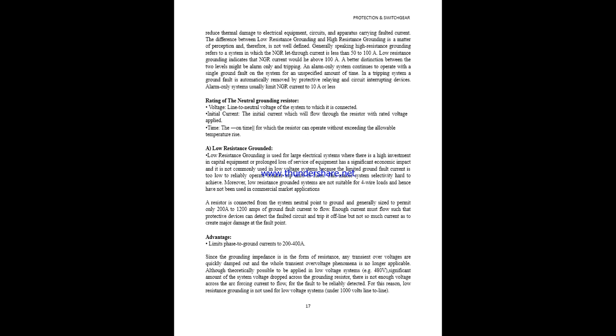There are two different types of resistance grounding, which are low resistance grounding and high resistance grounding. The ground fault current flows through either type of resistor, and when a single phase faults to ground, it will increase the phase to ground voltage of the remaining two phases. You can see it here. The difference between low resistance grounding and high resistance grounding should be very clear before we go for the analysis of the NGR current.